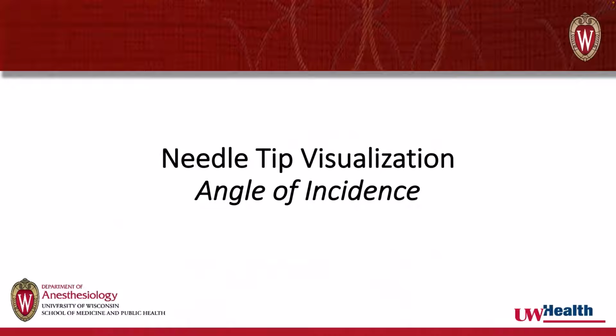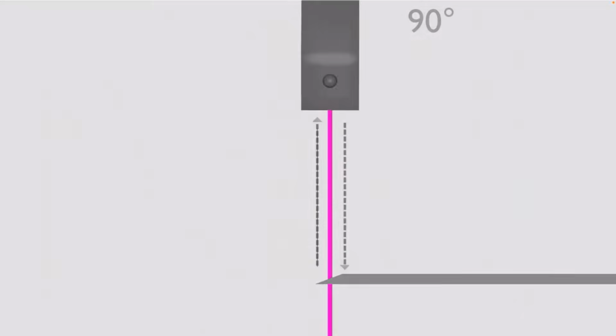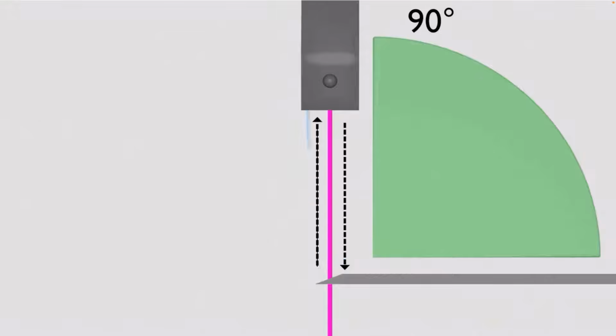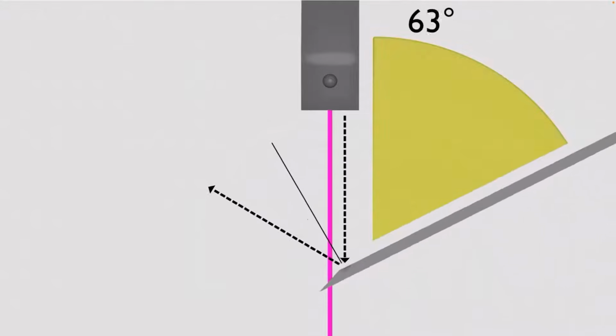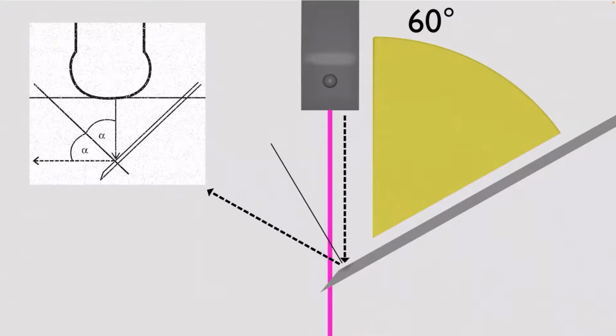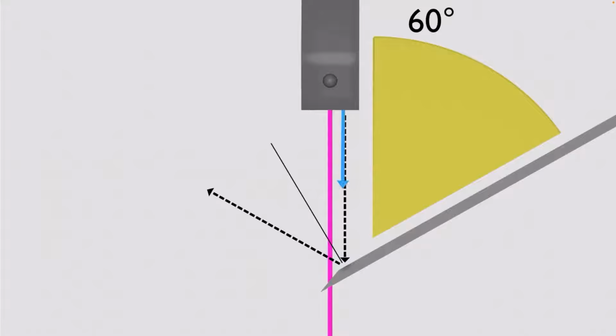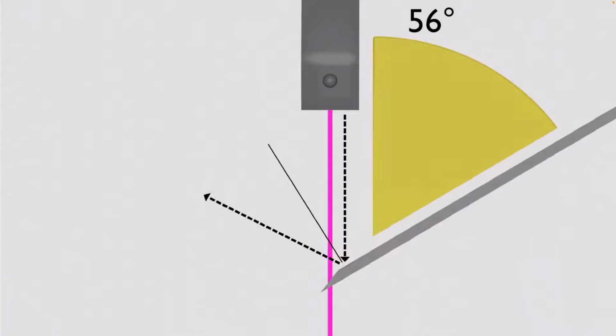All right, another really critical point has to do with what's called the angle of incidence or angle of inclination. And this has to do with the angle of the needle compared to the angle of the beam coming from the ultrasound. So if the needle is perpendicular to the ultrasound beam, your sound is going to go down, hit the needle, and come right back up, and you're going to have a very bright white needle tip, as the vast majority of that sound energy is going to return to the ultrasound probe. However, as the needle increases in steepness and the angle of inclination decreases, then more of that sound energy is going to be reflected away from the probe, and your needle tip is going to become less visible.